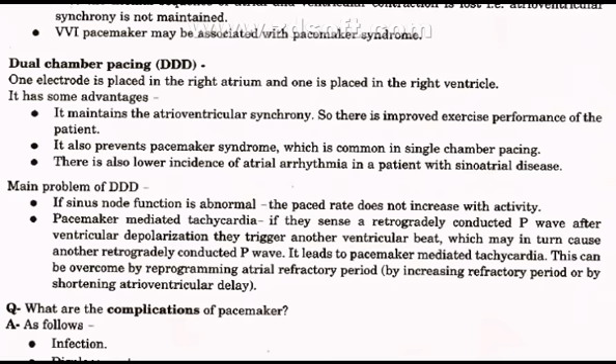Main problem of dual chamber pacing DDD: if sinus node function is abnormal, the paced rate does not increase with activity. Pacemaker mediated tachycardia: if they sense a retrogradely conducted P wave after ventricular depolarization, they trigger another ventricular beat, which may in turn cause another retrogradely conducted P wave. It leads to pacemaker-mediated tachycardia. This can be overcome by reprogramming the atrial refractory period, by increasing refractory period, or by shortening atrioventricular delay.